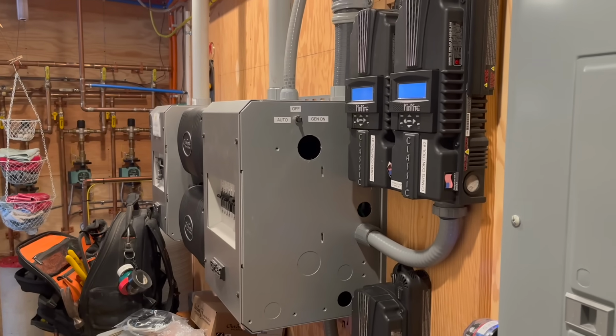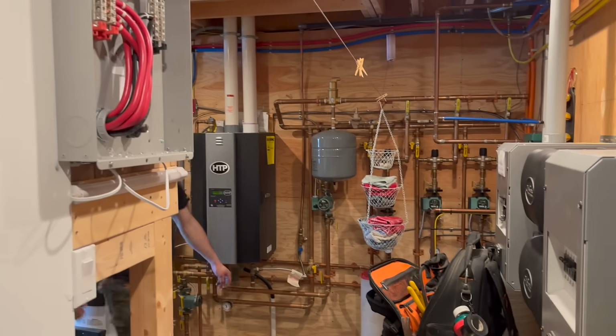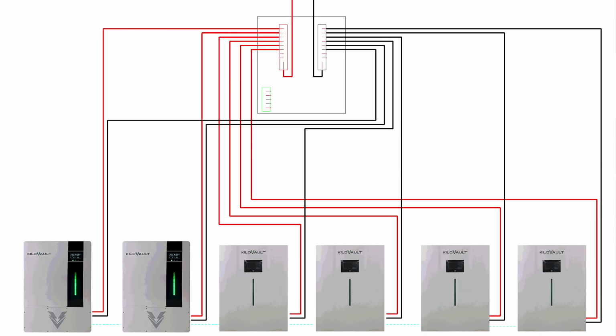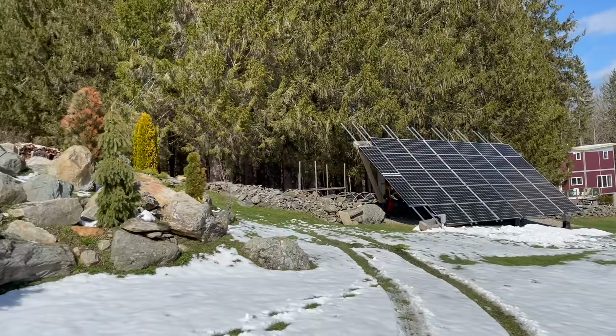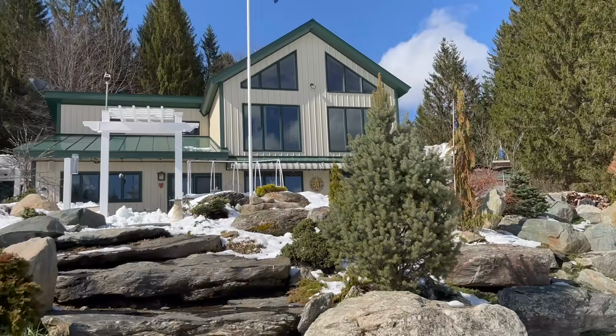Since the batteries are each 48 volts individually and all need to be wired in parallel, the system utilizes a Midnight lithium battery combiner box to bring all of the positives and all of the negatives to a common bus bar using equal length 1-aught cables. From the top of the buses runs a pair of 4-aught home run cables to get over to the inverter system. And with that, we have reached the end of our top to bottom tour of this wonderful off-grid system.